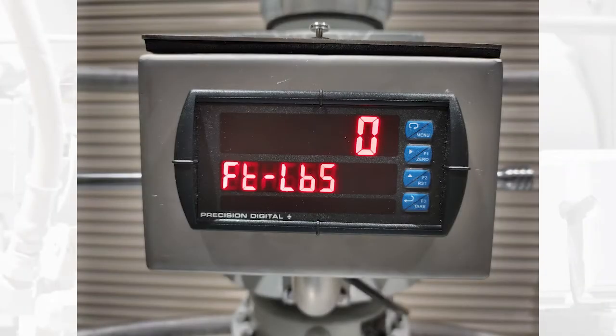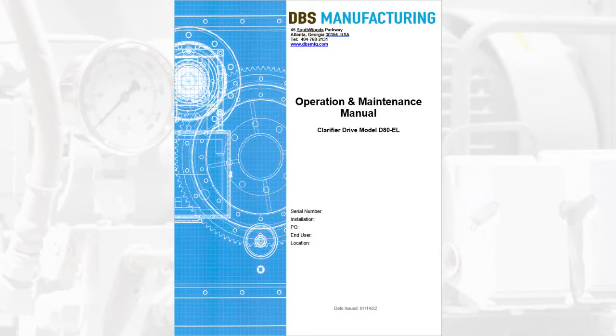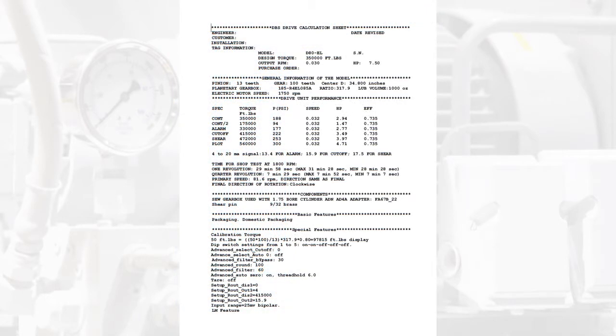Calibrating the torque meter requires it to be energized. Wire and energize the torque meter per manual instructions while following all proper safety protocols. DBS will provide a drive calculation sheet in the operation and maintenance manual for each drive unit. This sheet will provide the specific calibration information for your drive unit.